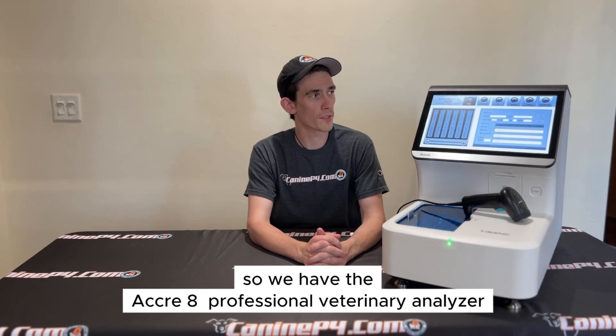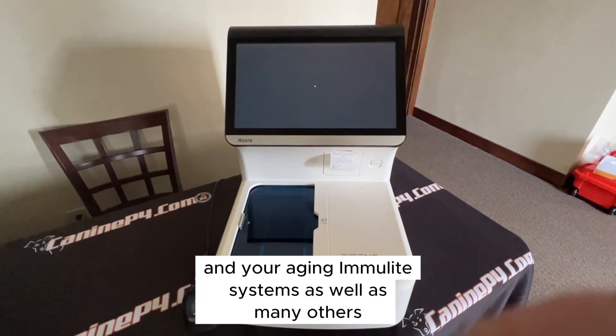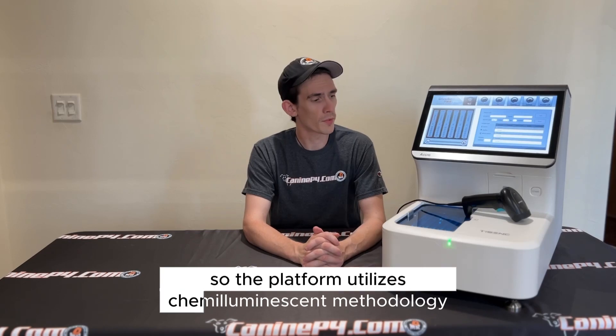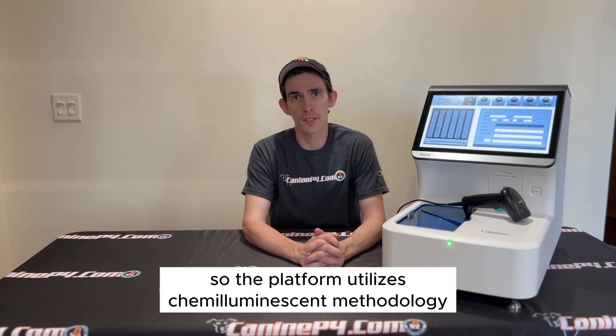So we have here a professional veterinary analyzer, the Accre8, designed to replace your Minividas and your aging Immulite systems, as well as many others. The platform utilizes chemiluminescent methodology, gold standard in the veterinary testing world, and produces results in as little as 25 minutes.